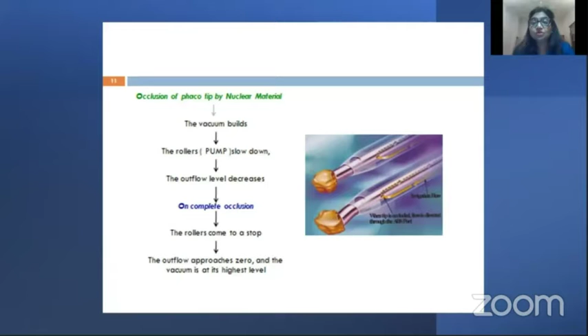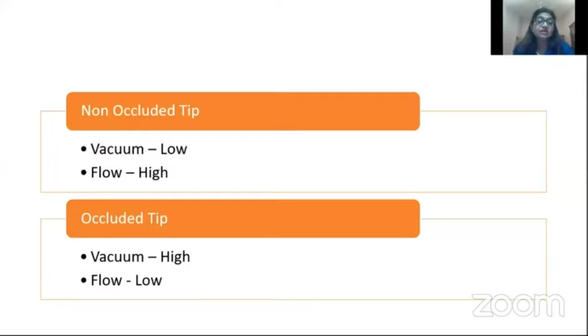So in short, a non-occluded tip will have a low vacuum and high flow rate, whereas when the tip is occluded, there will be high vacuum and the flow rate will be less. Now we need to understand what is surge. It is basically when the nuclear fragment comes and the tip gets occluded.